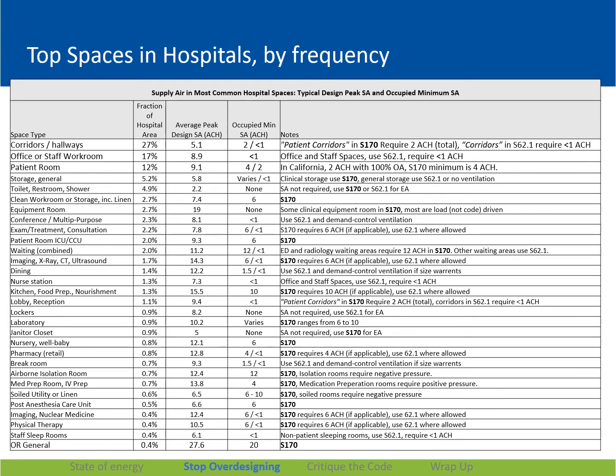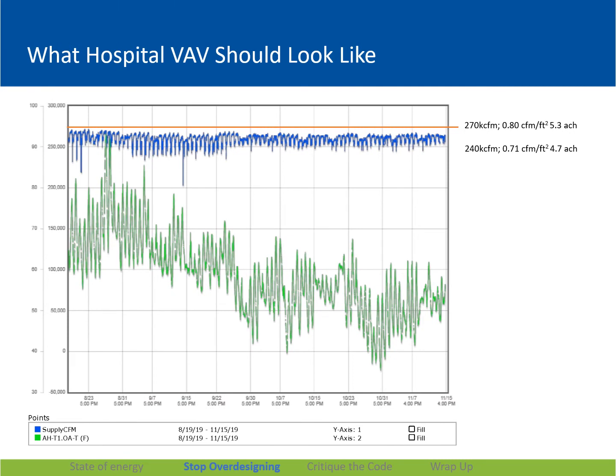And then, of course, the single most common space in hospitals is corridors. We have miles and miles of corridors. There's a quarter mile of corridor for every 100,000 square foot of hospitals. And our design engineers put in an average of 5 air changes, which is a lot of air. The code minimum is 2 air changes. So that is a 60% turn down opportunity between the peak and an overnight minimum. So let's go back to this chart.